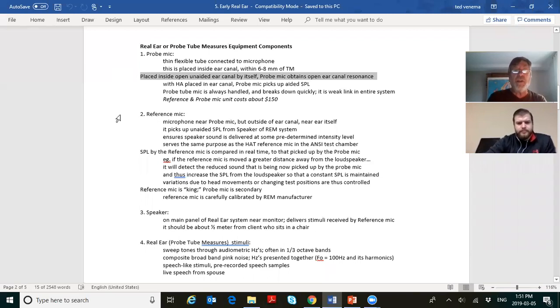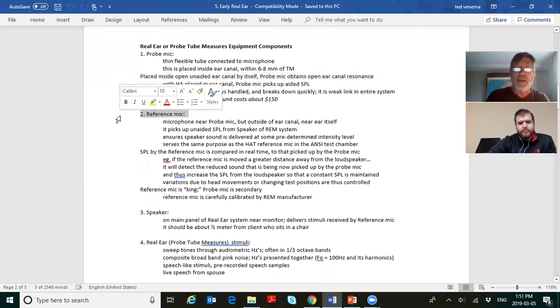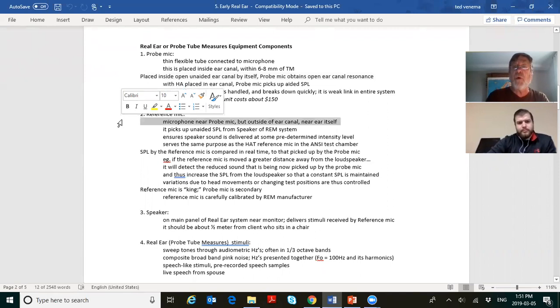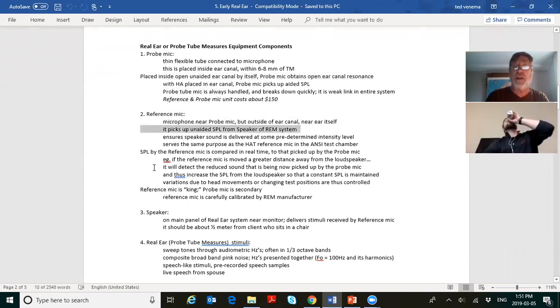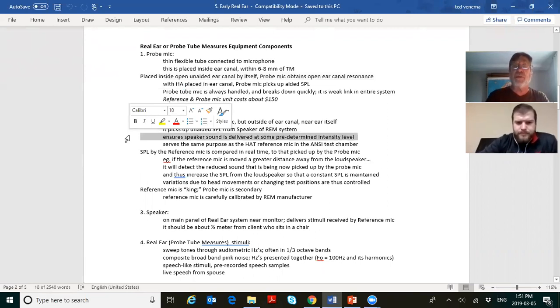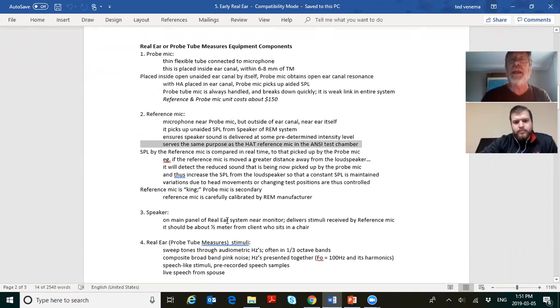So the probe mic and the reference mic are on the mic assembly. The reference mic is near the probe mic, but it's outside of the ear canal. It's near the ear, of course. It's on the little box. It picks up unaided SPL from the speaker. It ensures the speaker sound is delivered at some predetermined level. It serves the same purpose as the hearing aid test box reference mic in an ANSI test chamber. The very same purpose.